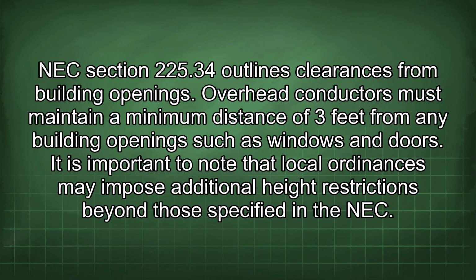NEC Section 225.34 outlines clearances from building openings. Overhead conductors must maintain a minimum distance of 3 feet from any building openings such as windows and doors. It is important to note that local ordinances may impose additional height restrictions beyond those specified in the NEC.